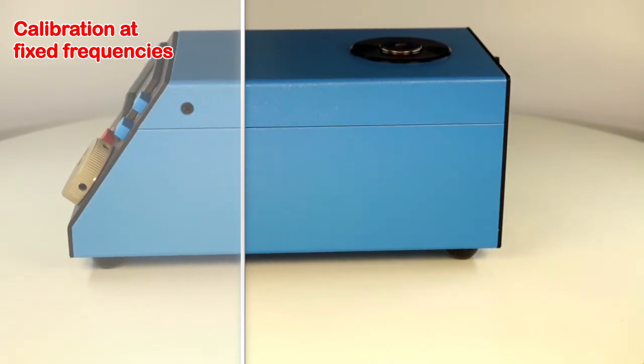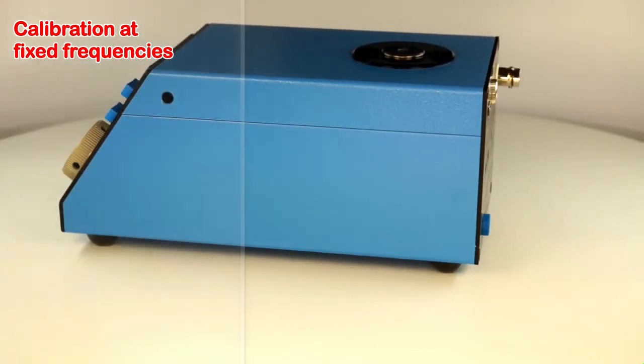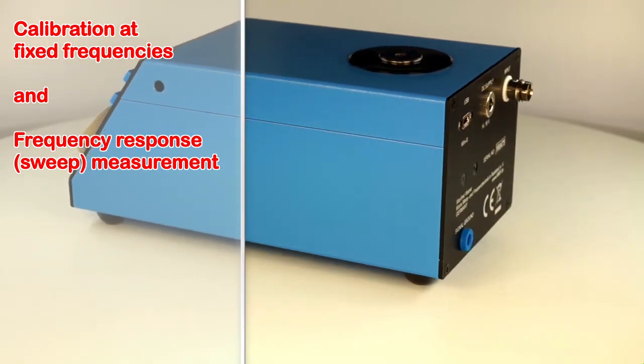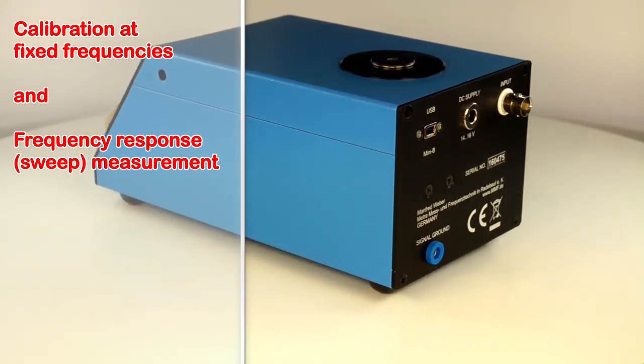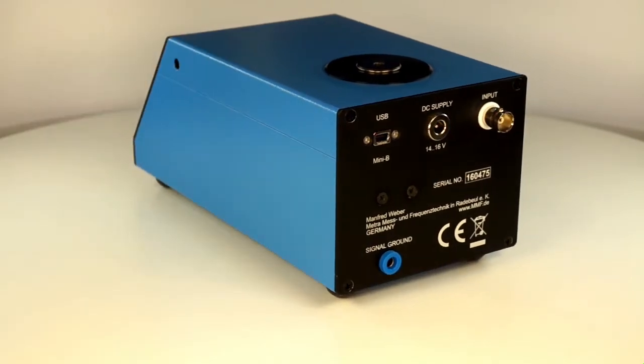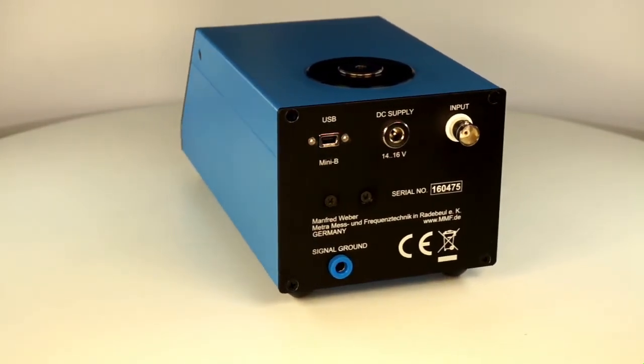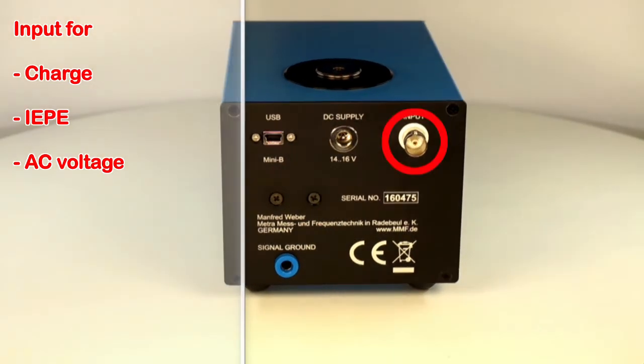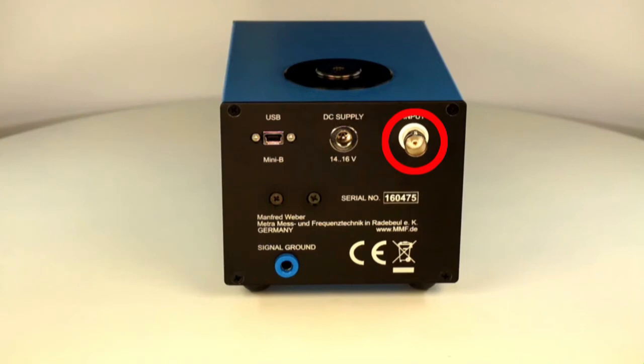Calibration is done at fixed frequencies which can be selected with the shuttle wheel. The VC120 can also record frequency response and sweep. At the back of the instrument you'll find a connection socket for the sensor signal. Compatible sensor types include piezo sensors with charge output, IEPE sensors and voltage signals. Here you'll also find a USB port for PC-controlled operation and a socket for using external power supply, which is also used for charging the built-in accumulator.